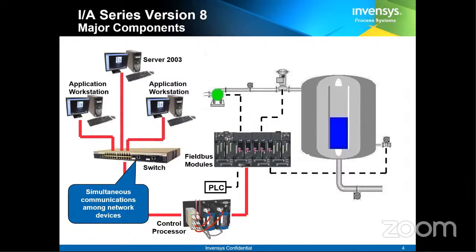So why are they programmed? The first purpose to make them managed or programmed is security. Each Ethernet port of this switch can be locked to a dedicated IP address. If any device with that particular IP address is connected, then only that port will work.